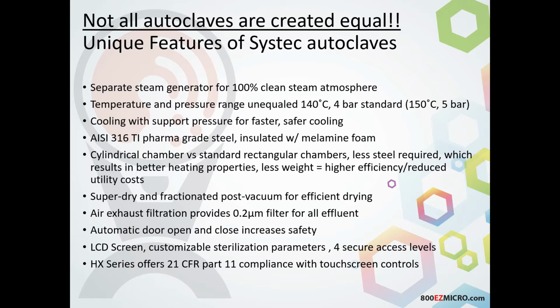We offer temperature and pressure range as standard up to 140 degrees C, 4 bar. So for any prion sterilization, the system is standard to be able to do so. We can also optionally go up to 150 degrees C, which would equate to 5 bar of pressure. This would be more for materials testing and any other special applications that you might have, as far as steam air mixture, blister packs, those type of things.